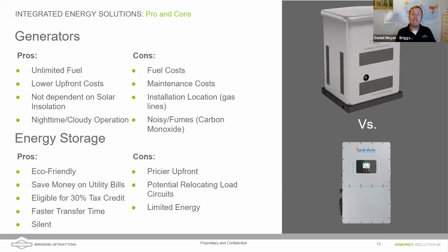But that load port can dynamically drop loads based on the energy reserves of the battery. There are additional load controls that can also drop loads based on power if the loads exceed the amount of power that will necessarily be pulled.